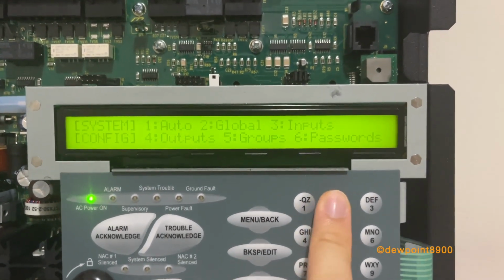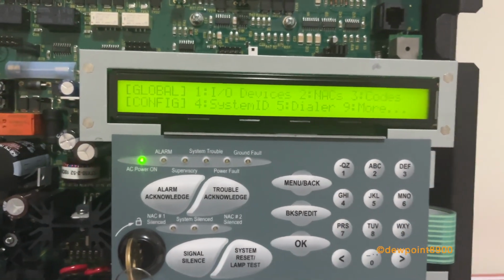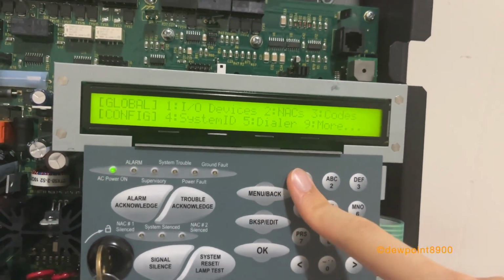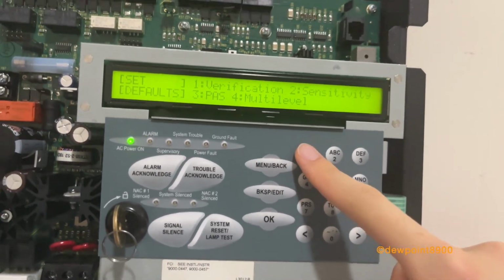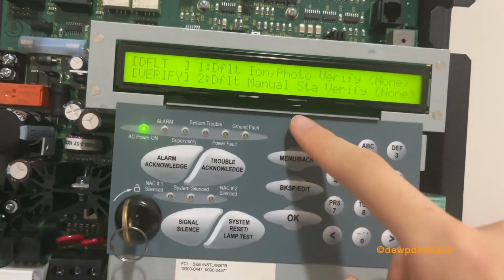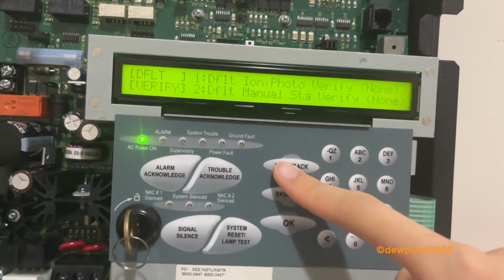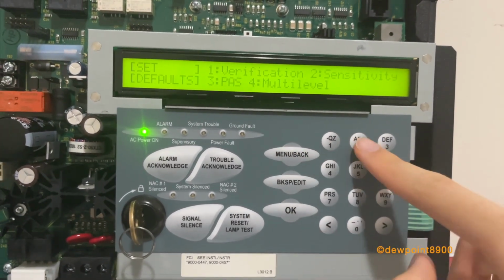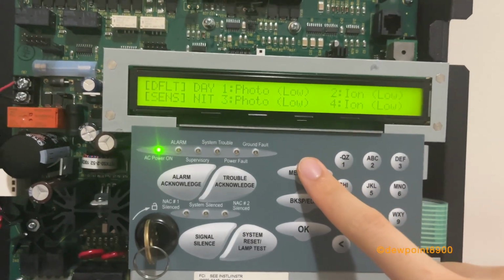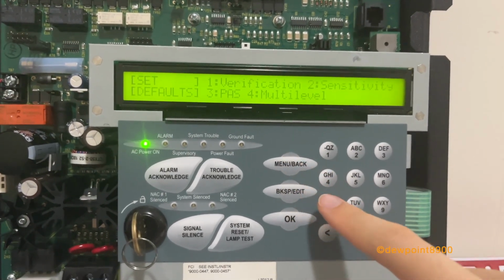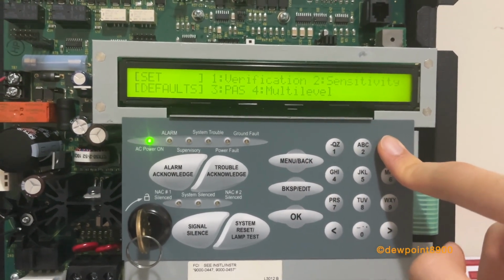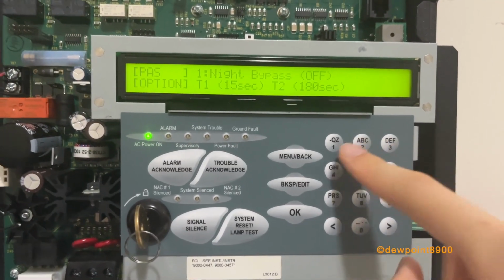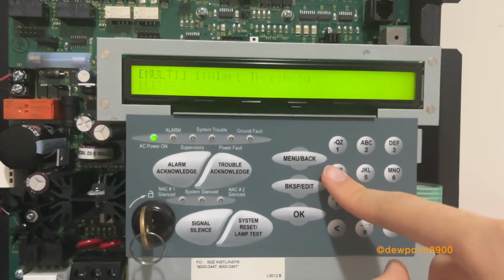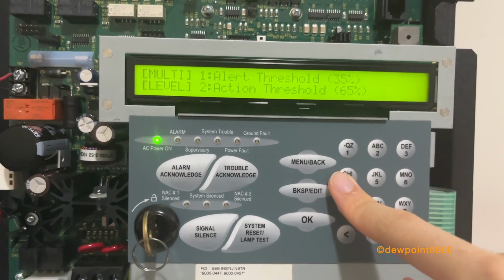Global are your system options. You start with I/O devices. You can set the verification for either the detectors or the manual stations. Sensitivity levels for detectors are all set to low. PAS or positive alarm sequence. And then multi-level, which sets the alert and action thresholds for the panel.